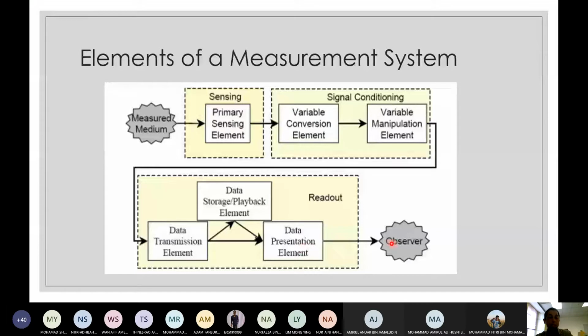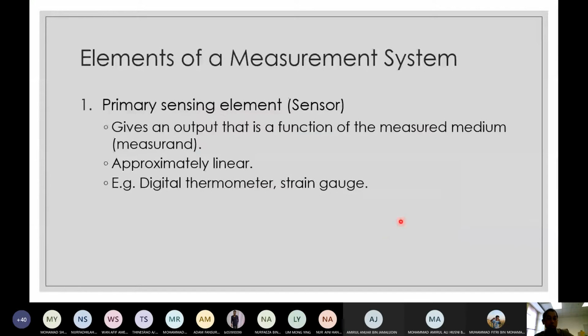Now let's look at the definition in more detail. The primary sensing element, we call it a sensor. It gives an output that is a function of the measured medium, which we also call the measurand, and it is approximately linear. What is meant by approximately linear? That means if the value goes up, the sensor should also have a higher reading. If the value goes down, the sensor should have a lower reading. It should be around proportional, so that our reading makes sense. Examples: digital thermometer and strain gauge.